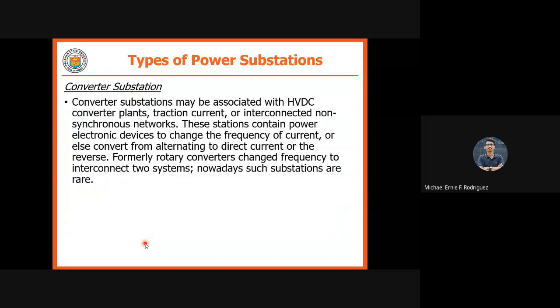This is associated with HVDC or high voltage direct current converter plants, traction current, or interconnected non-synchronous networks. So, example ng converter substation sa Pilipinas is, kung alam ninyo, nababanggit ko na ito noon, we have a 350 kilovolt high voltage direct current line connecting Luzon grid and Visayas grid. Okay? Meron tayong 350 kilovolts. That is high voltage direct current.